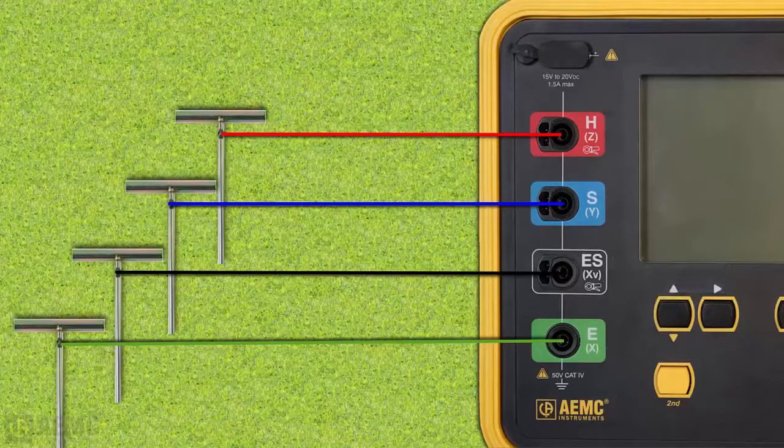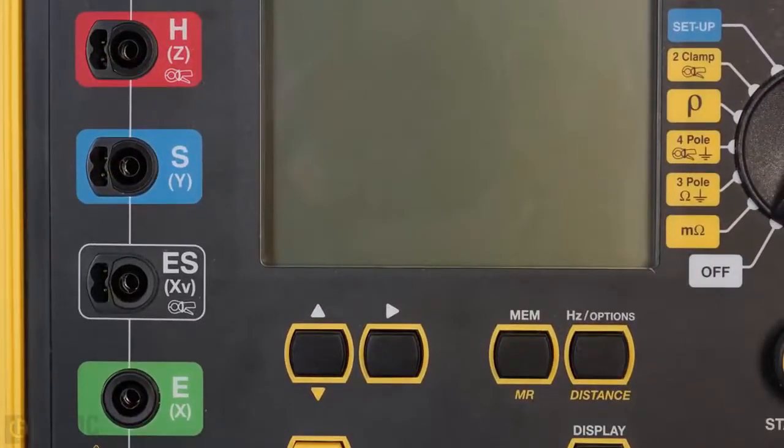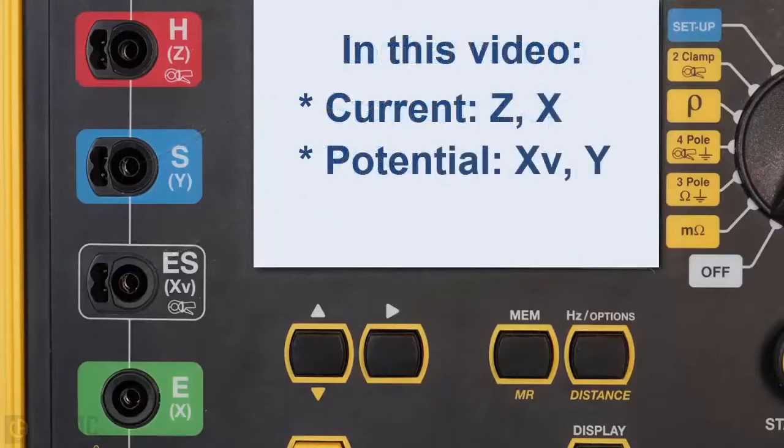Let's pause a moment to discuss how these terminals are labeled. According to international standards, the current terminals are called H and E. Some manufacturers label these terminals Z and X, while others use C1 and C2. Similarly, international standards define the potential terminals as S and ES. On some instruments these are labeled Y and XV, and on others P1 and P2. In this video, we will refer to the current terminals as Z and X, and the potential terminals as Xv and Y.